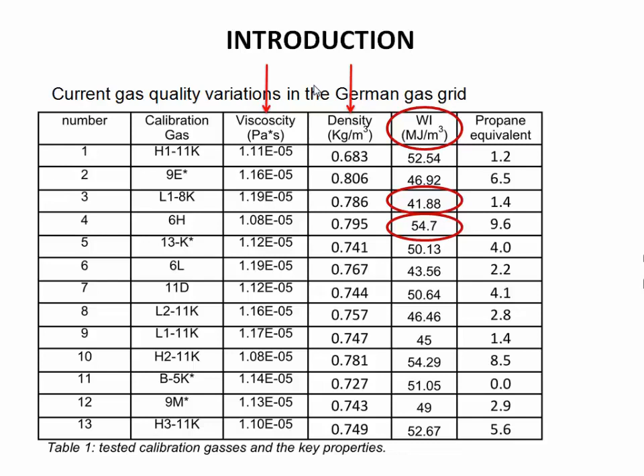So fortunately, there are some properties of the gas mixture, like the density and the viscosity, and we can correlate them more or less to the Wobbe index. So if you are capable of measuring one or more of these parameters, we should be able to also measure the Wobbe index. Of course, it's called monitoring the gas quality.